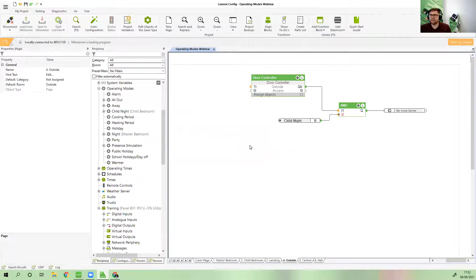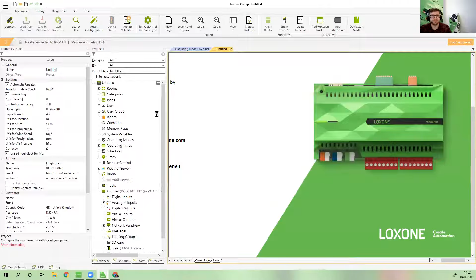But again, you would want to use lux level from outside, not lux level from inside, because again, that means that every time you turn the lights on manually, you're going to deactivate presence, which means that presence can't prolong the light staying on, which means that when you get in the bath and you're laying still, the lights will turn off on you. And you'll then, because they've been manually turned off, you'll have to get out of the bath to turn the lights on, which will again start the whole process again. Logic loops, oh, horrible things. So again, if you're going to do something like that, use outside lux, not inside lux.